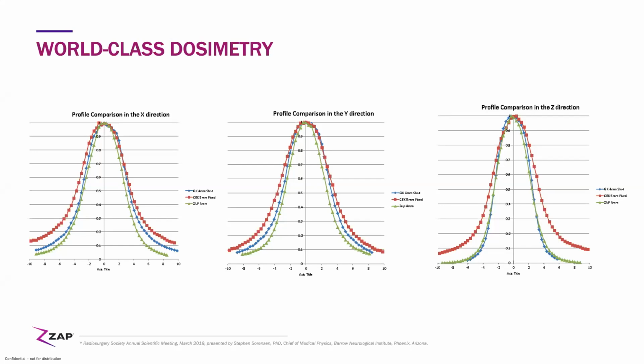Of course, the steeper the dose gradient, the better, because that's what gives you the ability to spare normal tissue in radiosurgery. If you look at these series of curves from the 3 cardinal axes, axial, coronal, and sagittal, you can see that in every plane, the ZAP-X, which is the green dots, had the steepest dose gradient. Here it's about the same as the Gamma Knife, but appreciably better than the CyberKnife, and would be appreciably better than your Linac-based systems, which we'll show you more. So with this constellation of properties, the ZAP-X delivers the tightest dosimetry, the least penumbra of any radiosurgical system today, which is going to be increasingly important as we go forward and treat ever smaller targets.